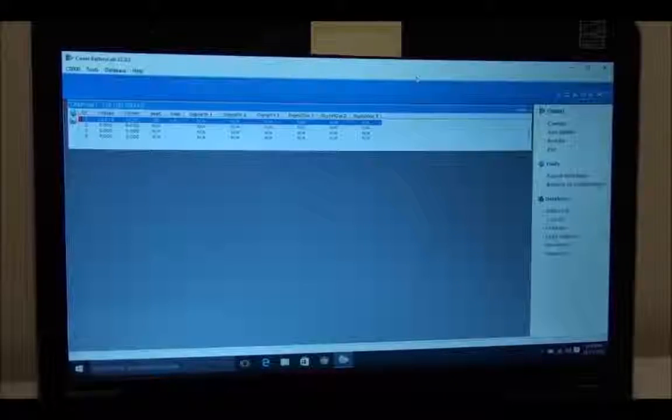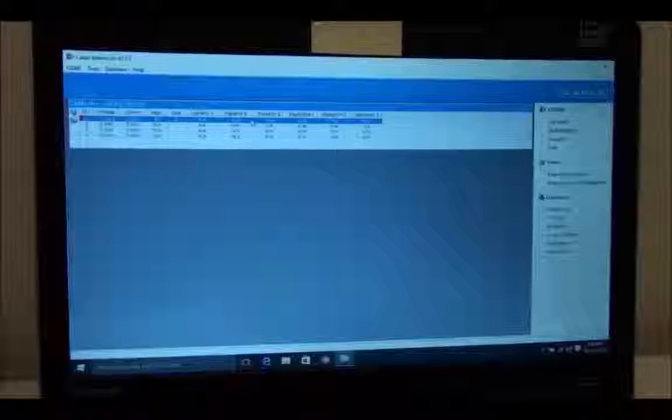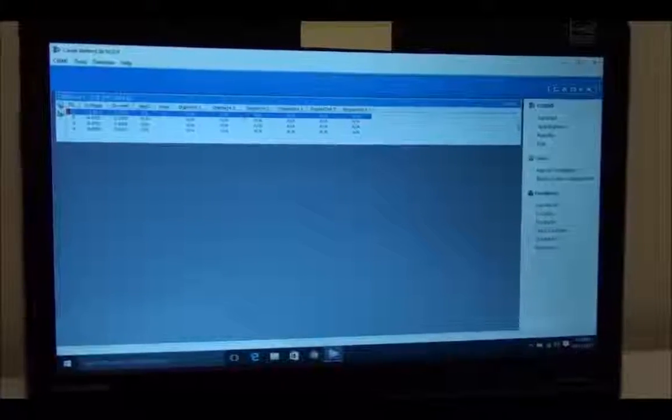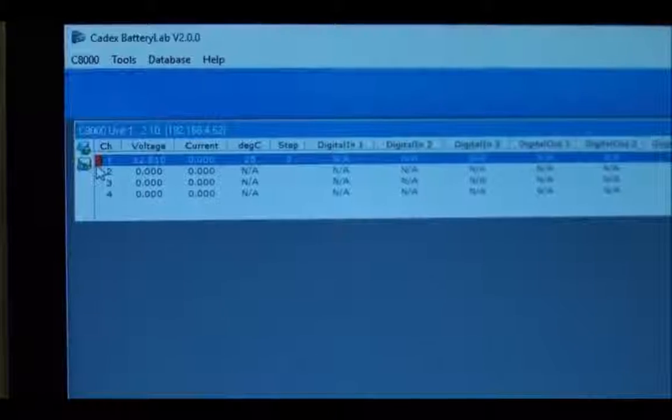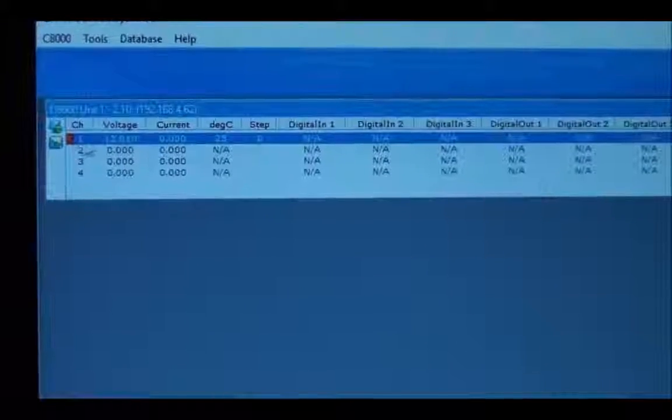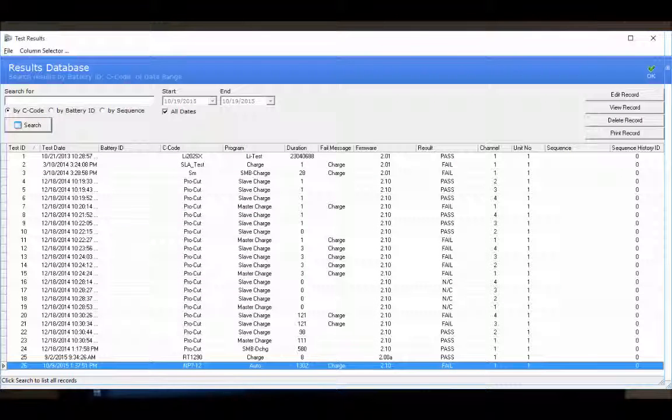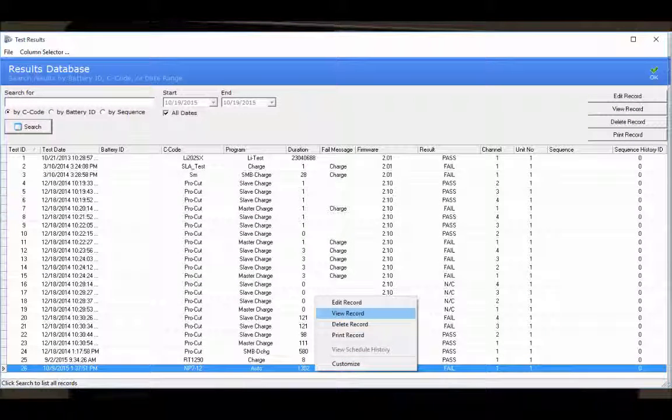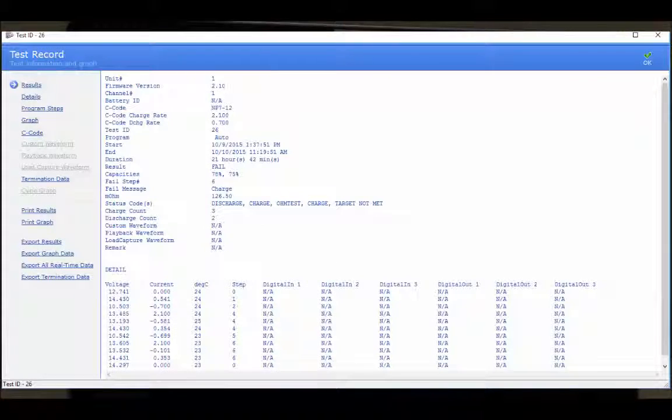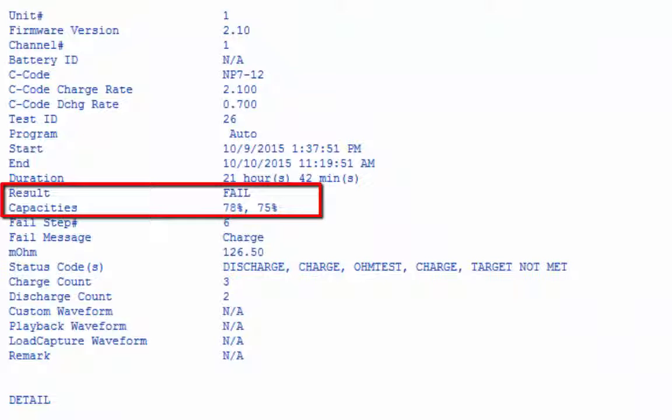From the software, you can see that this battery has finished. There's a red indicator here which shows that this battery actually failed the program. You can pull up the results on the right side, and the last one would be that test. You can see that this battery failed based on capacity. It got 78% on the first run and 75% on the second run.